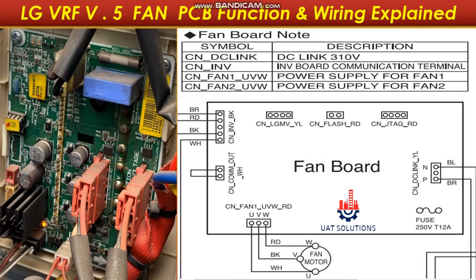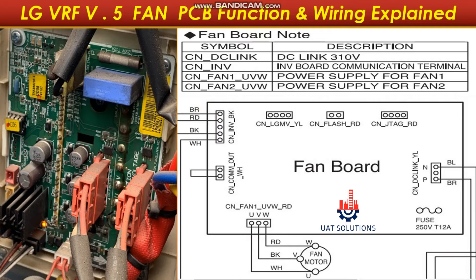Basic function of fan board is to run the condenser fan motor at variable speed. The fan speed is determined using the discharge temperature and pressure. The main PCB monitors the pressure and sends signal to inverter board, and inverter board sends commands accordingly to the fan board to run the fan on required speed.